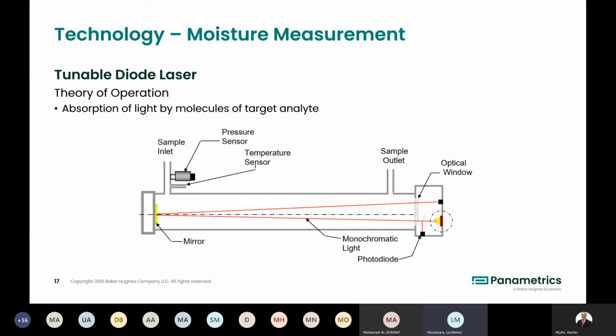It's pressure and temperature compensated. Whereas on the previous slide you saw the aluminium oxide sensors, which can measure at process pressures up to 340, 350 bar, here we have to make the measurement at atmospheric pressure, but we're able to do some pressure and temperature compensation on that. So that's the elevator speech on how the laser works. If you move to the next slide, Hunter.